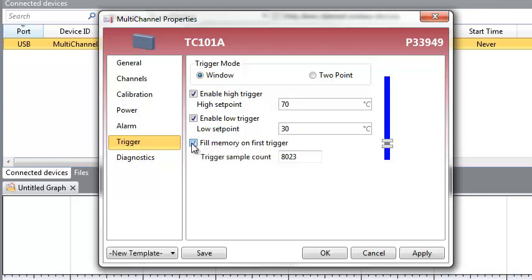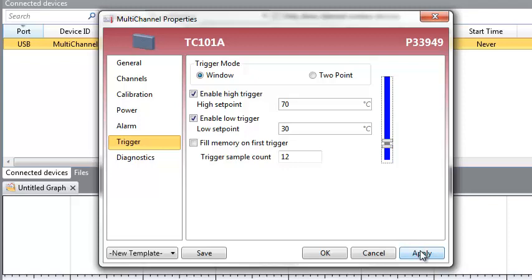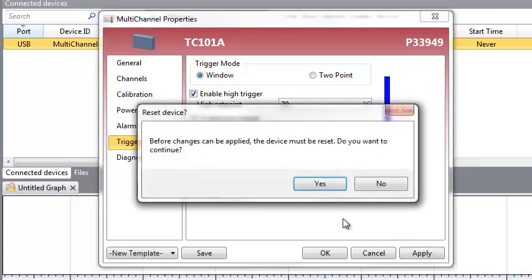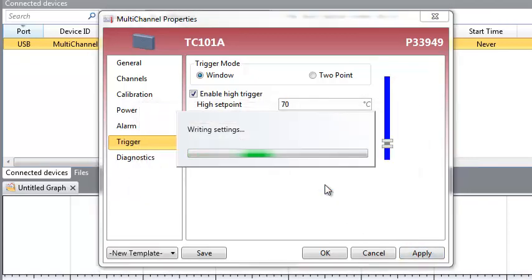For example, if you set a trigger sample count of 12, when the trigger threshold is met or exceeded, the logger will record 12 samples of data and then wait for the next trigger. Once you have these settings configured to fit your needs, simply click Apply in the bottom right corner to save your settings.